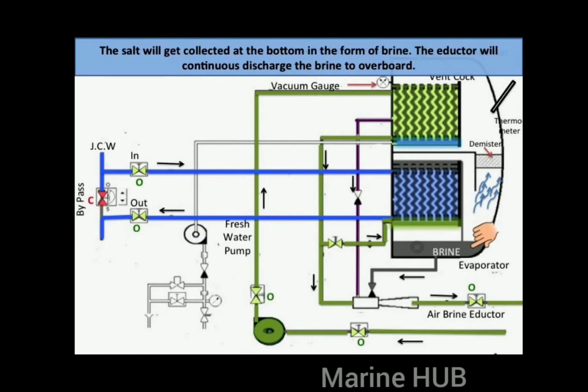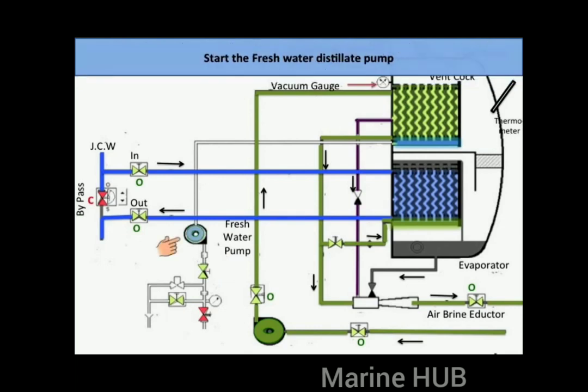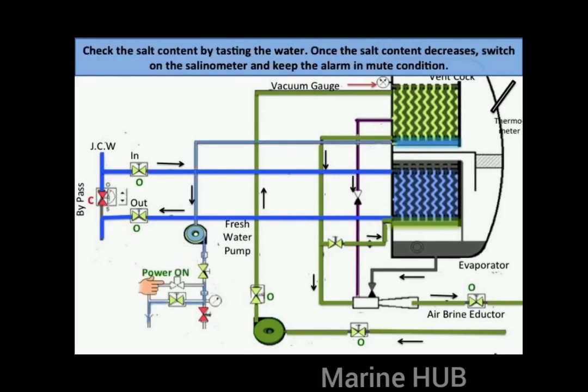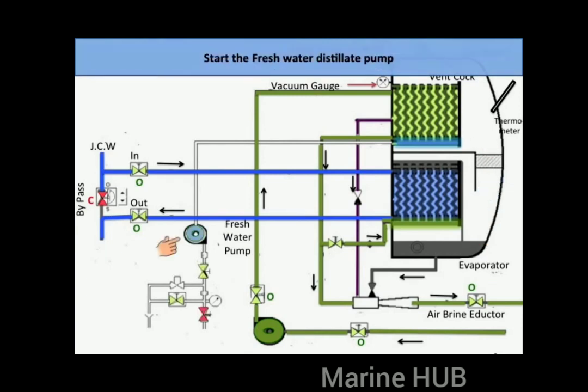The salt will collect at the bottom in the form of brine, and the eductor will continuously discharge the brine overboard. Open the fresh water distillate pump discharge valve and the bypass valve of the salinometer to initially check the salt content, keeping the discharge valve to the fresh water tank shut. Start the fresh water distillate pump and check the salt content by tasting the water. Once the salt content decreases, switch on the salinometer and keep the alarm on mute. Shut the bypass valve and activate the alarm once the salinometer reading goes below the alarm limit, then open the fresh water tank filling valve so the generated fresh water collects in the desired tank.